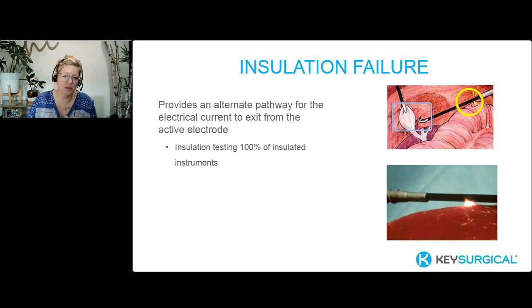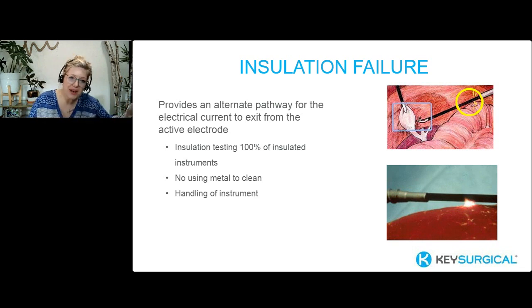In the OR, this is totally us, right? Not using metal to clean. When we're scraping, scratching, doing anything, not using metal to clean any of our instruments really can damage that insulation quickly. I had a conversation with a person about eschar, and they're like, eschar doesn't bother me. I just scrape and scratch it off. Sometimes I use the back of my knife, and I'm like, well, it's not great for our insulated instruments. That insulation is very close to the active tip that we're using. The handling of the instrument, again, if you're not quick enough to grab it from the surgeon, it gets set down, sometimes it can fall off.